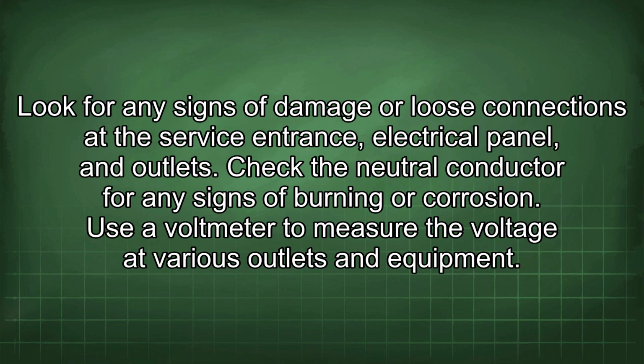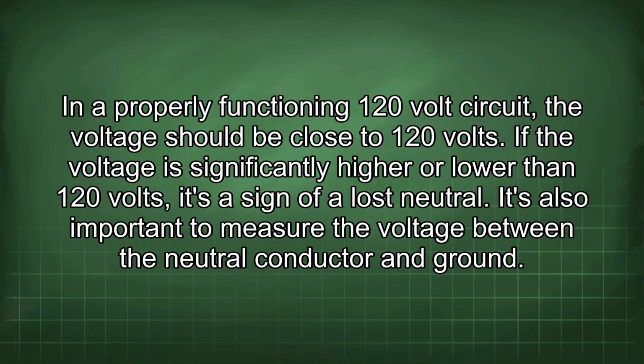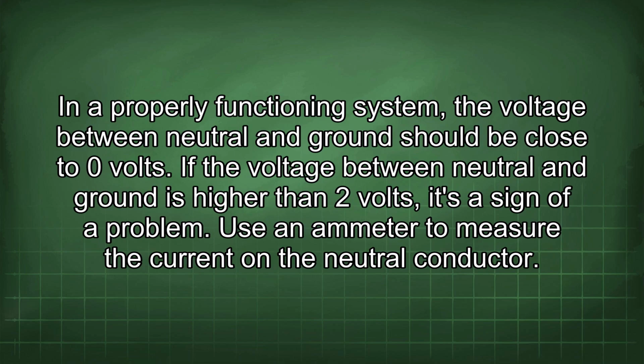Once the symptoms have been identified, the next step is to perform a visual inspection of the electrical system. Look for any signs of damage or loose connections at the service entrance, electrical panel, and outlets. Check the neutral conductor for any signs of burning or corrosion. Use a voltmeter to measure the voltage of various outlets and equipment. In a properly functioning 120-volt circuit, the voltage should be close to 120 volts. If the voltage is significantly higher or lower than 120 volts, it's a sign of a lost neutral.